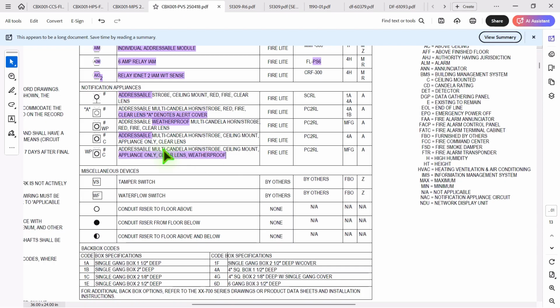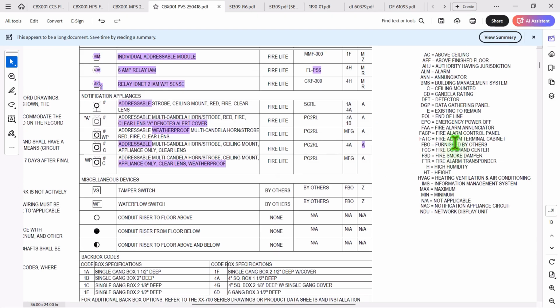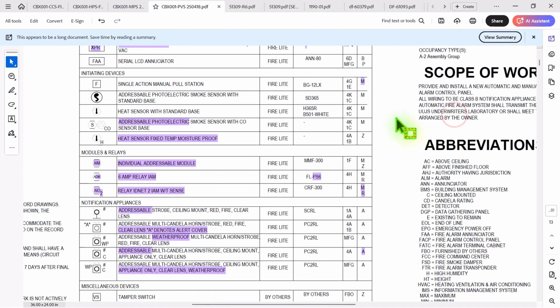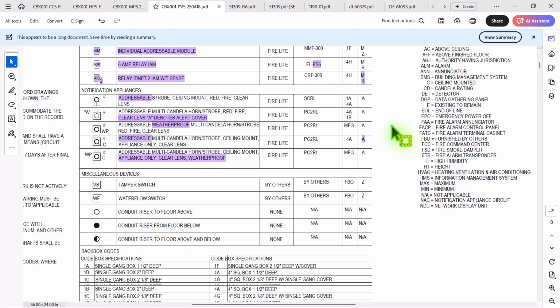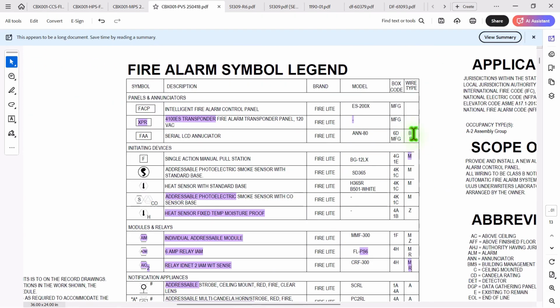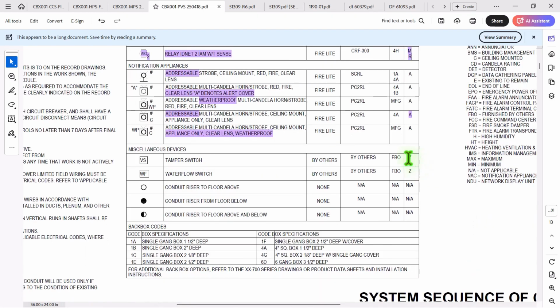The model numbers are good. The wire for the strobes will not be A, they'll be C - this is all C wire. But the relay will get a wire, the R wire, to depict the relay, and the remote annunciator will get a B wire and a P wire, just like this is a B wire and a P wire. Tamper switches are going to get A wires because the module is what's connecting to that - actually, put it as an A wire for both the tamper switch and water flow.